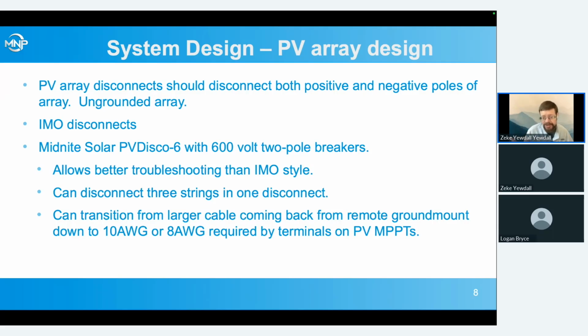Both poles have to be in series to get the 600 volt rating, but using one on the negative and one on the positive of the same string, they're still in series. It doesn't matter if they're directly in series right next to each other, or if one is on the negative and one's on the positive. So that way you can get 3 of those breakers in one disconnect and disconnect 3 strings all at once. And for troubleshooting, you can measure each string individually and turn on and off each string individually if you open the cover. So that's kind of nice versus the IMO where you can't turn on and off individual strings for troubleshooting.